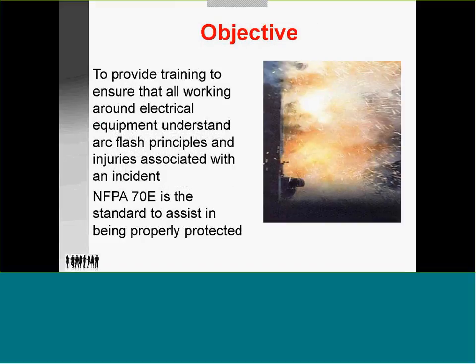So the objective here is providing training to ensure that all those working around electrical equipment understand arc flash principles and the injuries associated with the incident. NFPA 70E is the standard to assist. It starts at 240 volt 3-phase or greater, with one of 208 3-phase. When they came out with the 2015 edition, they dropped it down to 50 volts or greater that PPE must be worn. It doesn't have to be a full suit on the lower end. You will need it as you open up active or energized panels.